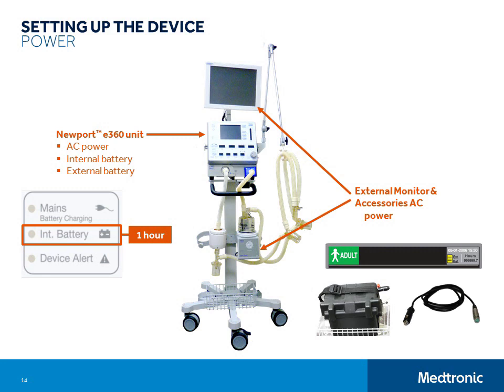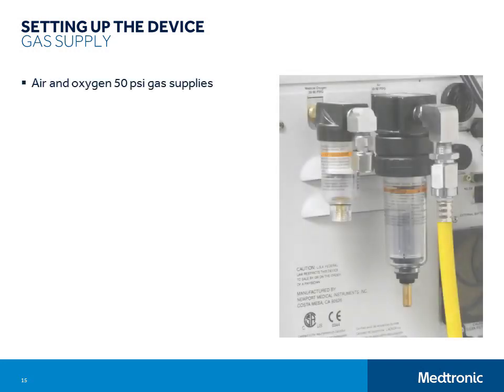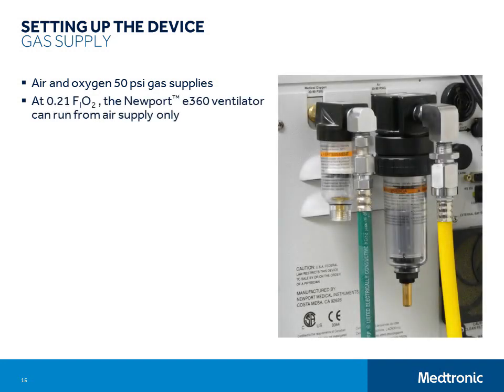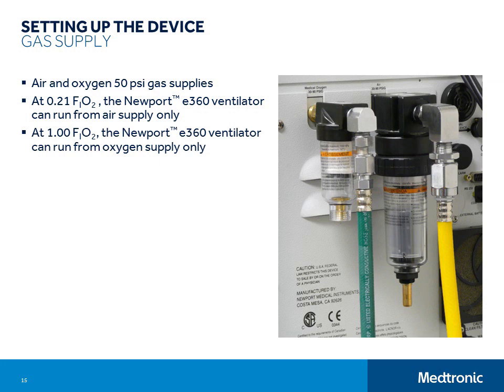External battery use is in. Next, we'll connect the gas supplies. The E360 ventilator is designed for use with both air and oxygen 50 psi gas supplies. But when you are ventilating at 21% oxygen, the E360 can run from an air supply with no oxygen connected. And when ventilating at 100% oxygen, the E360 can run from an oxygen supply with no air connected.